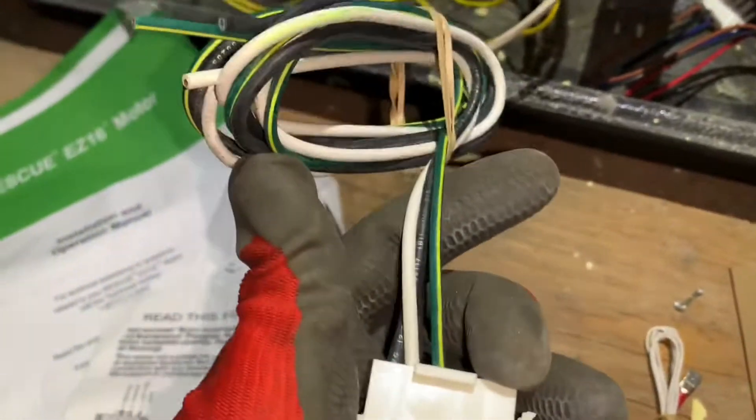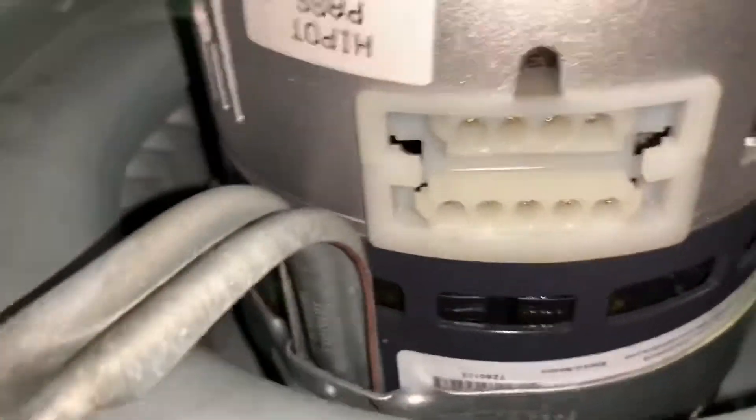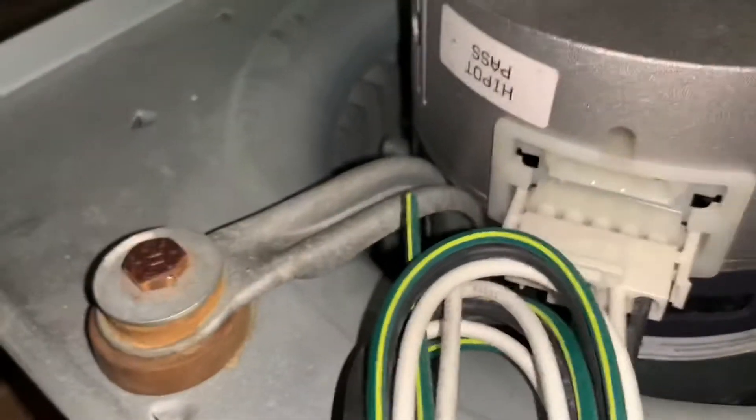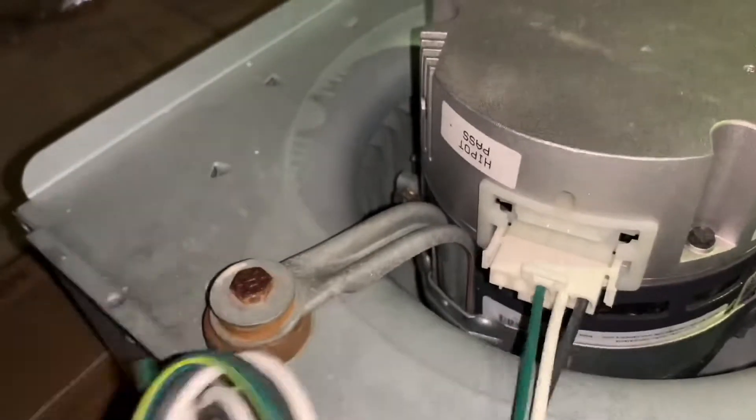Don't mind the wire colors — they're arbitrary here. This new motor is dual voltage, so the colors don't necessarily indicate 120V. Also note that the plug connections on the new motor are different. There's a power connection and a signal or communication connection. The bottom connector is the power connection. Once you have the right orientation, it clips right in. Make sure it's properly secured — you should feel it click.